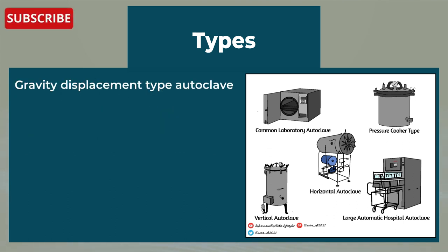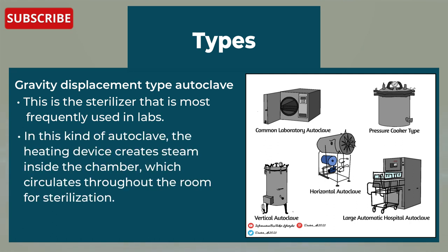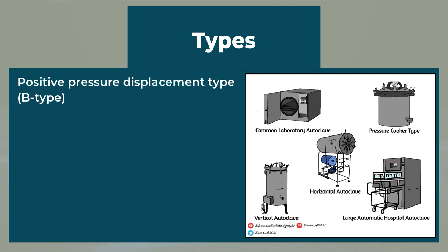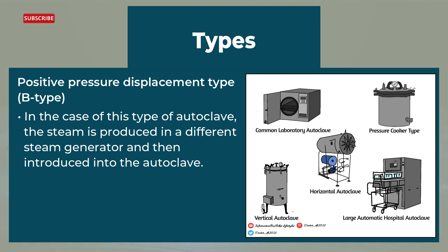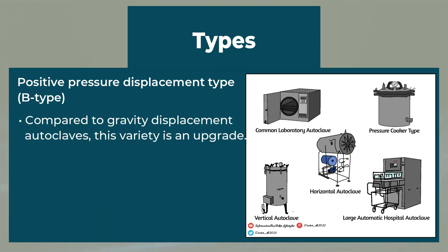Next comes the gravity displacement type autoclave, which is the sterilizer most frequently used in labs. In this kind of autoclave, the heating device creates steam inside the chamber, which circulates throughout the room for sterilization. Comparatively, this kind of sterilizer is less expensive than others. Next is the positive pressure displacement type. In this type, steam is produced in a separate steam generator and then introduced into the autoclave. This autoclave is quicker because the steam can be produced in just a few seconds, and it is an upgrade compared to gravity displacement autoclaves.